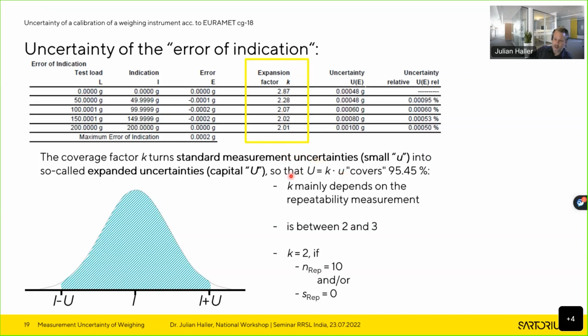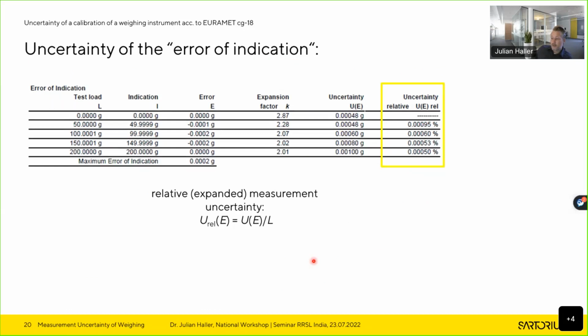And it depends, at least for the calibration of weighing instruments, mainly on the result of the repeatability measurement. It should then be in the range between 2 and 3, as you see it here. And if you have a sufficiently reliable repeatability measurement, which is the case if you do 10 repetitions, or if you determine a standard deviation of 0, then k equals 2. And finally, we do also state the relative expanded uncertainty. That's not necessary, but sometimes requested, which is actually just dividing the expanded uncertainty by the respective test load. So you have something in percent of the test load.